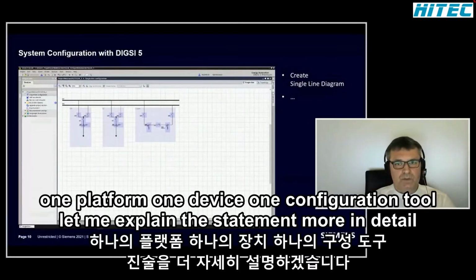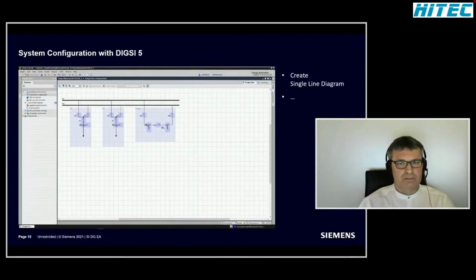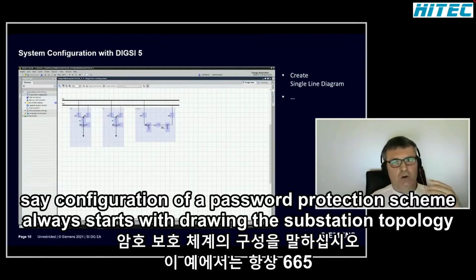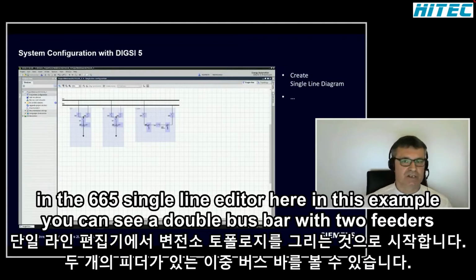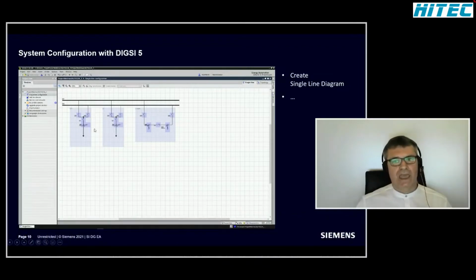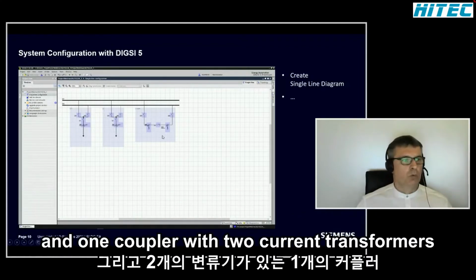One platform, one device, one configuration tool. Let me explain the statement in more detail. The configuration of a busbar protection scheme always starts with drawing the substation topology in the DIGSI 5 single line editor. Here in this example, you can see a double busbar with 2 feeders and 1 coupler with 2 current transformers.